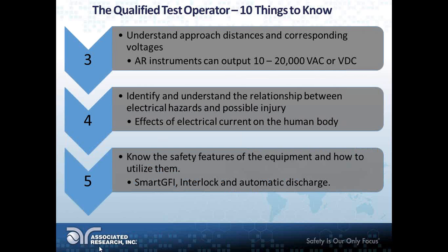All right, so delving into the next round, let's look at the next few. Understand approach distances and corresponding voltages. What I mean by approach distances is from NFPA, the National Fire Protection Association, and the NEC, the National Electrical Code. Safety approach distances are basically how close you can get to that circuit, and it really depends on voltage level as well. With regards to approach distances, for anything between, I want to say, 750 and 15,000 volts, the prohibited approach boundary is 2 feet 2 inches.